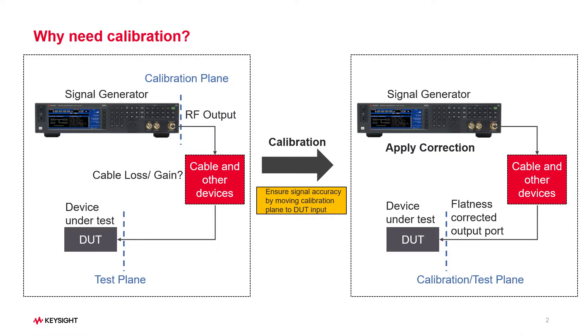You are probably all too familiar with issues caused by long connections. The longer the cable, the higher the loss. When you add components between the signal generator and the DUT, the calibration plane and the test plane are not the same plane. You must correct the difference between the two planes. The flatness correction can compensate the transmission loss and help achieve robust flatness performance as the input to your DUT.